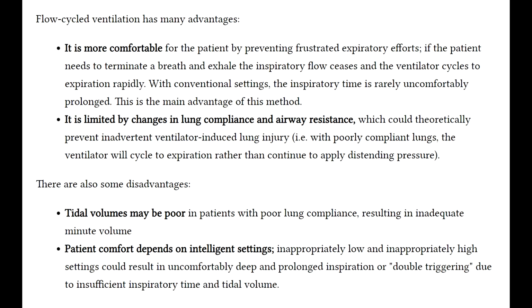Flow cycled ventilation has many advantages. It is more comfortable for the patient by preventing frustrated expiratory efforts. If the patient needs to terminate a breath and exhale, the inspiratory flow ceases and the ventilator cycles to expiration rapidly. With conventional settings, the inspiratory time is rarely uncomfortably prolonged. This is the main advantage of this method. It is also limited by changes in lung compliance and airway resistance, which could theoretically prevent inadvertent ventilator-induced lung injury.